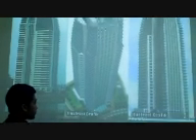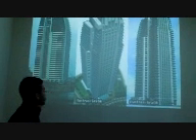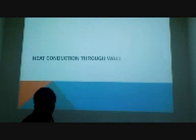This is the graphic illustration of the building, and this one is the real one. The first calculation that I've done is heat conduction through wall. This is the table from the AutoCAD.